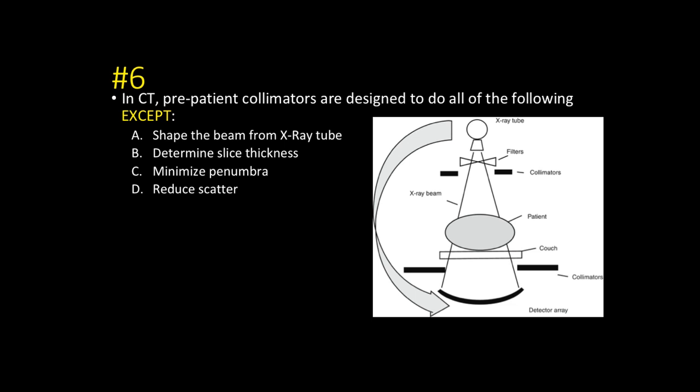Number six: in CT, pre-patient collimators are designed to do all of the following except reduce scatter. Options A, B, and C are all jobs of the pre-patient collimator: it shapes the beam from the x-ray tube, determines slice thickness, and minimizes penumbra. Penumbra is the portion of the x-ray beam that hits the patient but does not reach the detector — it's excess dose being wasted. The post-patient collimators, also called pre-detector collimators, are the ones that reduce scatter.